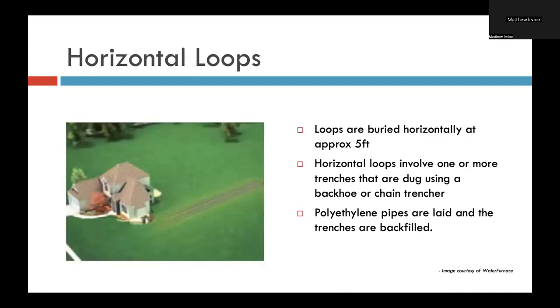Next, please. So horizontal loops. These loops are typically buried at approximately 5 or 6 feet deep. These horizontal loops are going to involve one, but typically more, trenches that are dug using a backhoe or chain trencher. And then the polyethylene pipes are laid and the trenches are backfilled. If you can see the visual representation of the earth loop stretching out behind that house, imagine that trench is 5 or 6 feet wide, 5 or 6 feet deep, and 300 feet long. And in that trench, you would get two tons of geothermal loop capacity. Next.